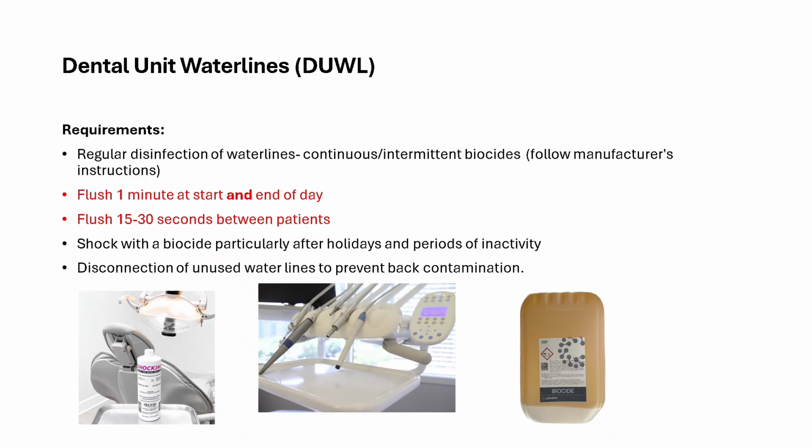It's recommended also to flush the water lines for 1 minute at the start and end of the day, and flush for 15 to 30 seconds between patients to remove any stagnant water. It's also important to shock water lines after periods of inactivity. So shocking means using a high level of disinfectant, and always make sure to disconnect unused water lines.